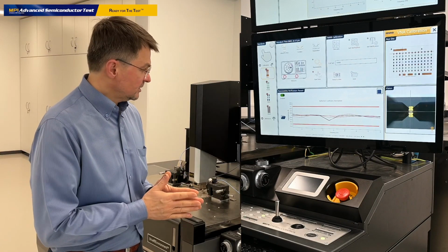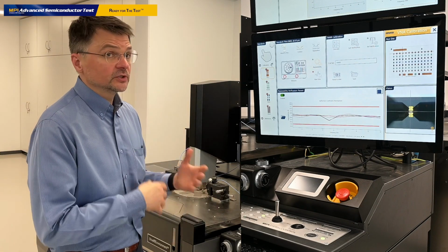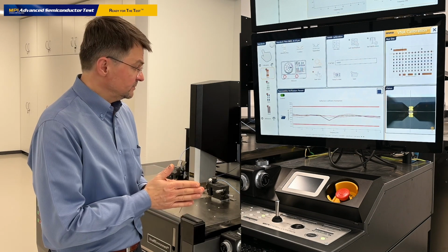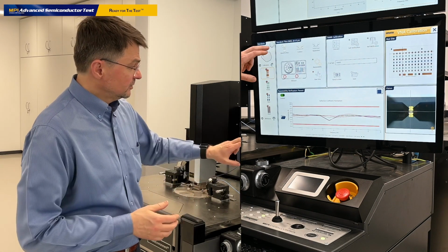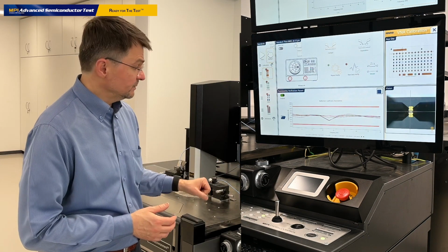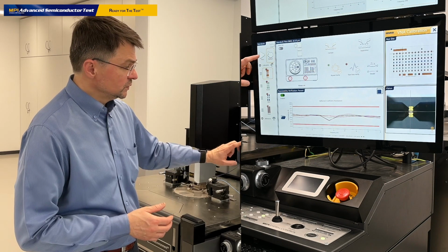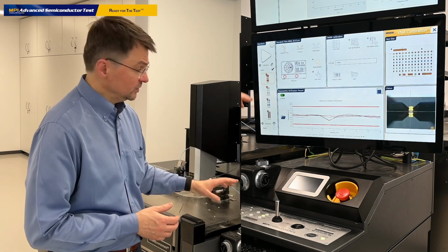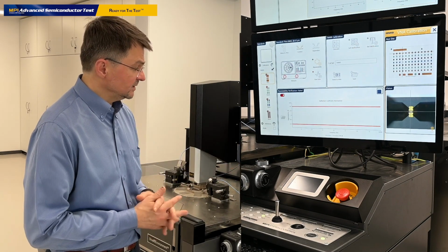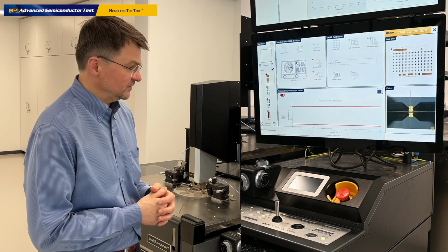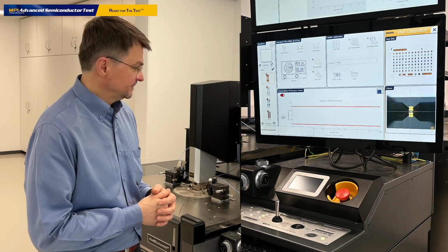And now let us check how easy it is to switch from the manual control over the calibration process to the fully automated control by the calibration process. To do so, we simply go to the settings on our calibration player and switch from manual to the automated control. Go back to the execution window and press the button Run. It's as simple as playing a list of your favorite songs on your MP3 player.